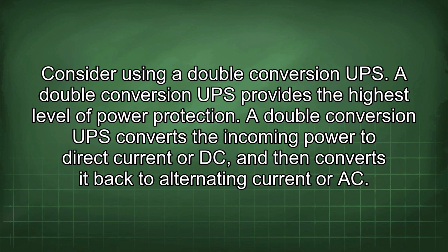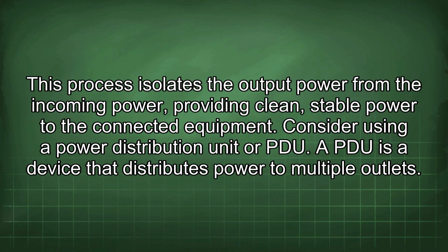Consider using a double conversion UPS. A double conversion UPS provides the highest level of power protection. A double conversion UPS converts the incoming power to direct current, or DC, and then converts it back to alternating current, or AC. This process isolates the output power from the incoming power, providing clean, stable power to the connected equipment.